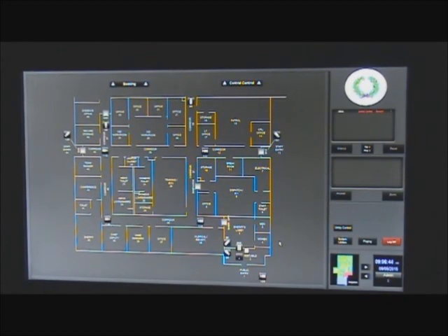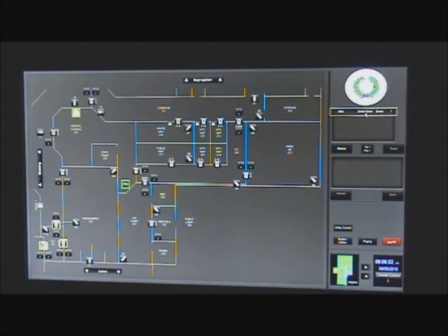Give me an indication. Awesome. So that quick, we now have an alarm in queue. When I select the alarm, it scrolls to the area or the door that has the problem, wherever the alarm is. I hit silence. Function, alarm silence. And then when I reset the door and I physically shut the door, it goes resettable. So the little reset popped up next to it, and I can just simply click it again and hit reset. Function, alarm reset. And that clears the problem or the alarm that was in queue.